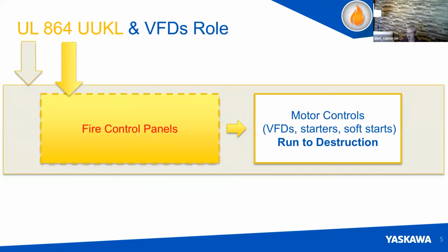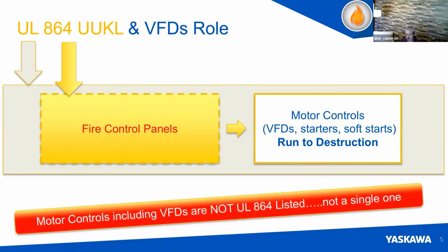So yes, the drives do a lot of the heavy lifting in the smoke control, the fire control solution, with the purging of the smoke, controlling the motor speed and the fans. But UL 864 does not apply to motor controls or transducers or any other end device that is simply doing what it's told by the fire control panel. So you won't find a single motor control or VFD that is UL 864 listed. It's not a thing. It makes sense that it could be, but it's not. So just keep that in mind. If someone asks you for that, that's not really something that applies to drives.